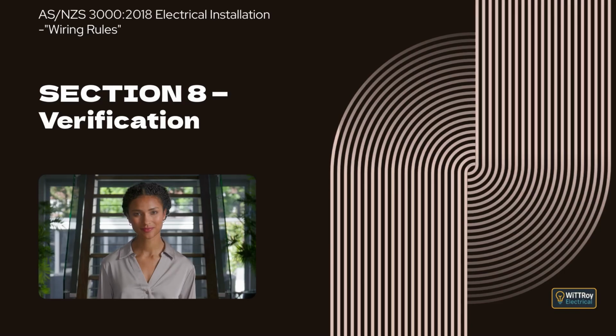The general condition of electrical equipment is assessed to identify signs of damage that could affect safe operation, and to confirm that unused electrical equipment has been disconnected. The clause then moves to consumer mains. These checks include confirming that the current carrying capacity is adequate, that voltage drop is appropriate for the size of the conductors, and that underground installations have suitable enclosure, burial depth, and mechanical protection.